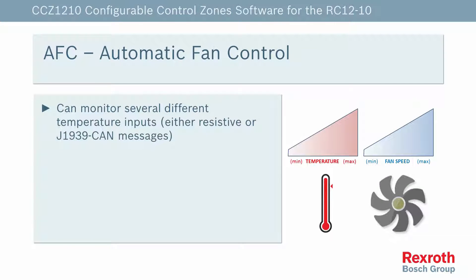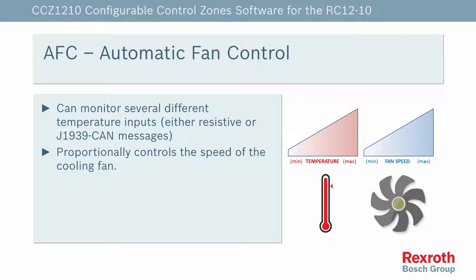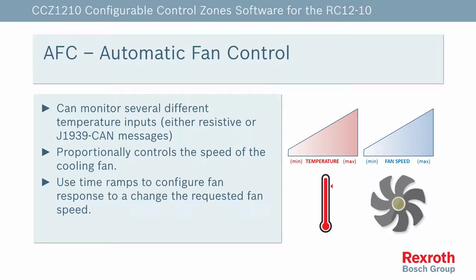The automatic fan control can monitor several different temperature inputs, either resistive or J1939 CAN messages, to proportionally control the speed of the cooling fan. Using time ramps, you can configure how quickly the fan responds to change in the requested fan speed.